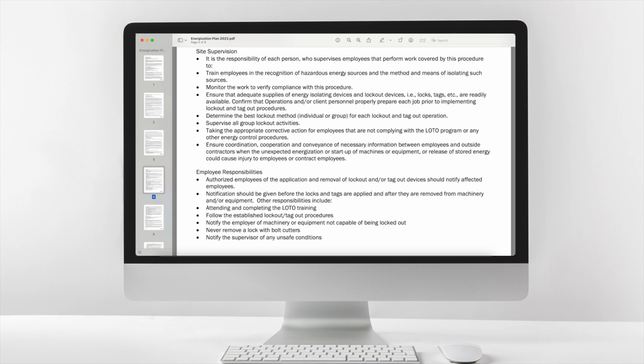Monitor the work to verify compliance with this procedure. Ensure that adequate supplies of energy isolating devices and lockout devices, i.e., locks, tags, etc., are readily available. Confirm that operations and/or client personnel properly prepare each job prior to implementing lockout and tagout procedures. Determine the best lockout method, individual or group, for each lockout and tagout operation. Supervise all group lockout activities.